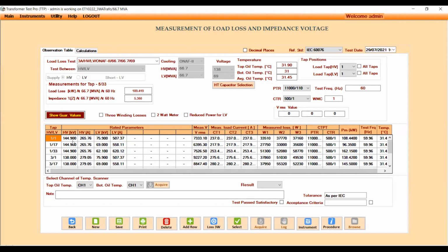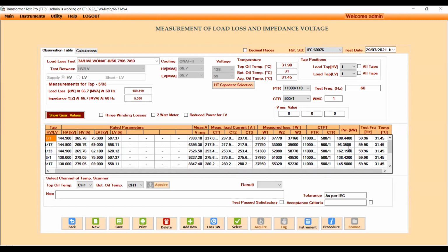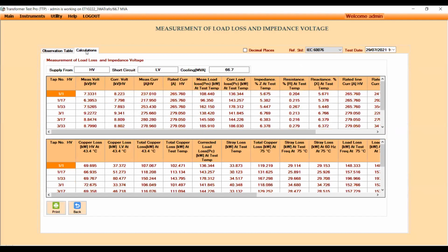Again, the same way, friends, you raise the voltage in such a way that the rated current flows in the other winding, and then you have the acquire button at the bottom, and you'll be in a position to get the values for various parameters: the measured voltage, the measured current, the measured loss, then the ratios for the current and voltage, the measured power, the test frequency, and the temperature at which the test has been taken. Once this has been done, next is to click on the tab on the top, that is calculations, and click on the calculations tab.